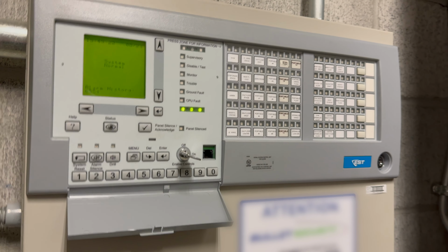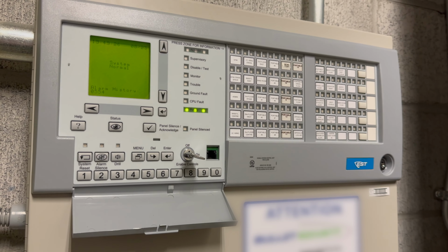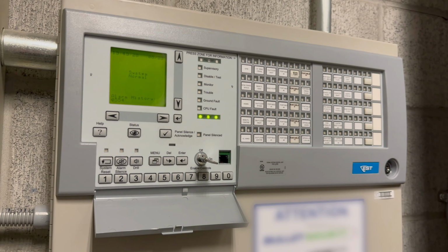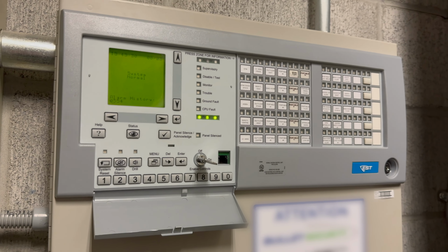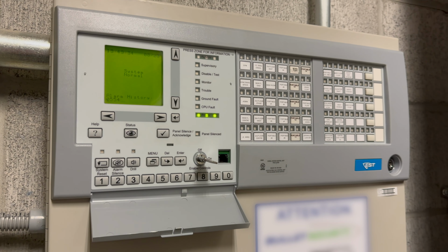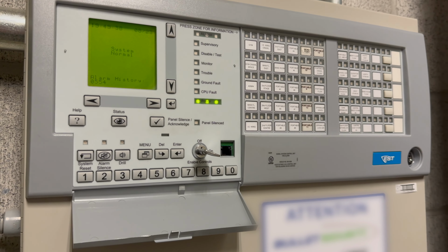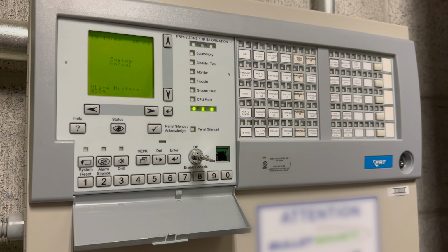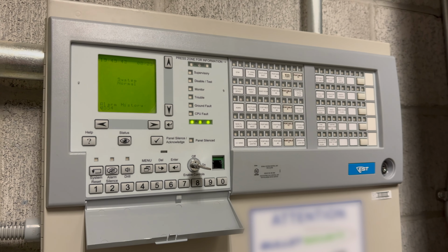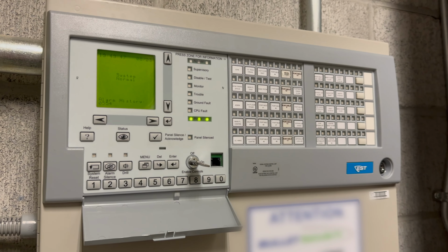Today we're going to be doing a quick fire alarm test here. We're not going to get to hear anything because we're going to disable it. We're just going to be testing how the monitoring company is receiving the alarms, because since the situation at one of our high schools where the sprinkler system froze and blew up and did not call the fire department because it only put a trouble through to the monitoring company, this has prompted more of an investigation because we've switched monitoring companies. So we've gone around and tested every school.